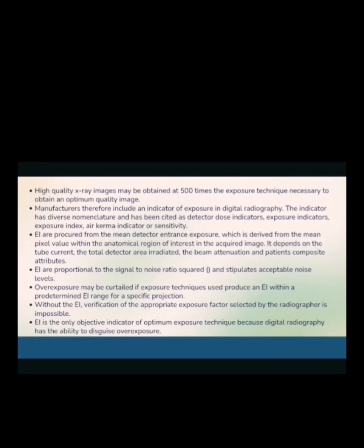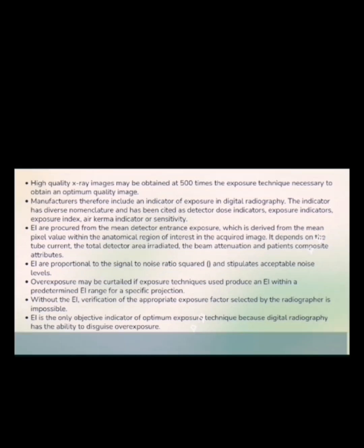On the other hand, the wide dynamic exposure latitude in digital radiography created a dearth in observable cues of exposure techniques. Therefore, high-quality X-ray images may be obtained at 500 times the exposure technique that is necessary to obtain an optimum quality image. Hence, knowledge learned about exposure technique from analog radiography can no longer be applied to digital radiography. Looking at the X-ray image alone will not provide information about exposure technique.